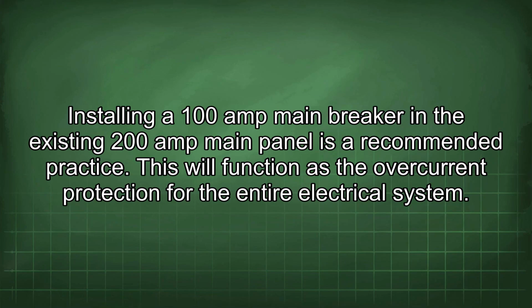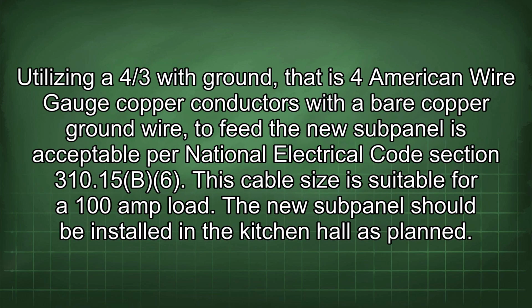Installing a 100 amp main breaker in the existing 200 amp main panel is a recommended practice. This will function as the overcurrent protection for the entire electrical system. Utilizing a 4/3 with ground, that is 4 American wire gauge copper conductors with a bare copper ground wire, to feed the new subpanel is acceptable per National Electrical Code Section 310.15(B)(6). This cable size is suitable for a 100 amp load.